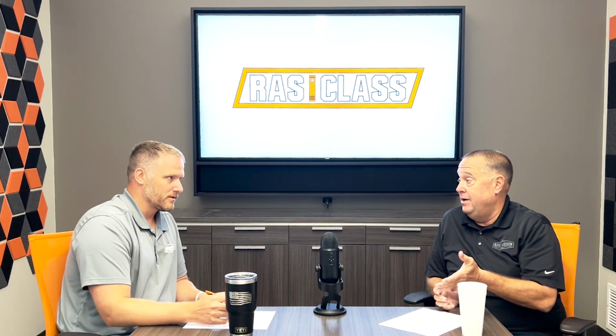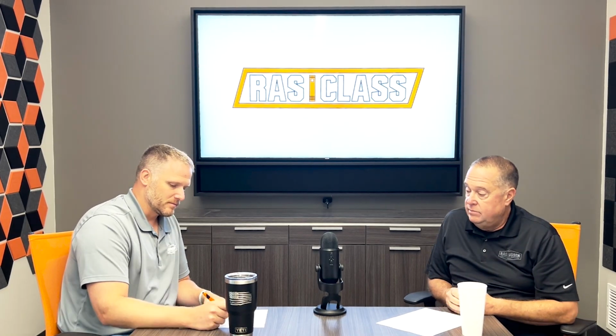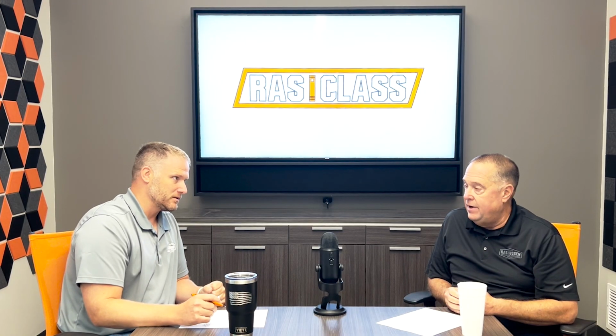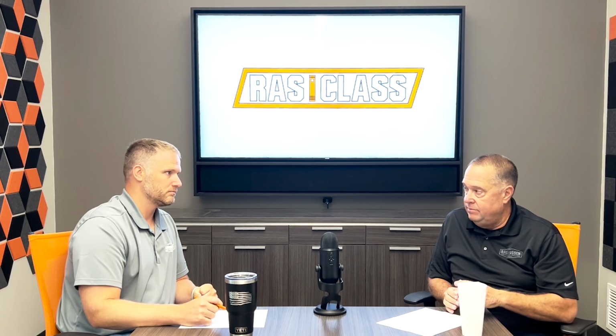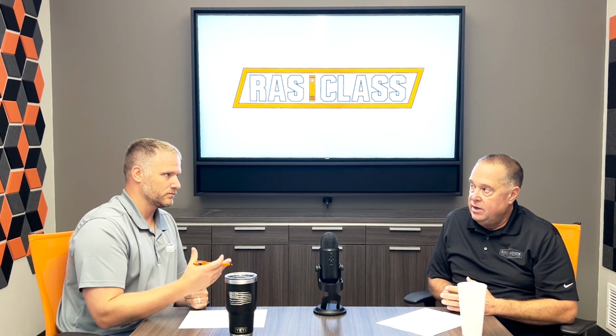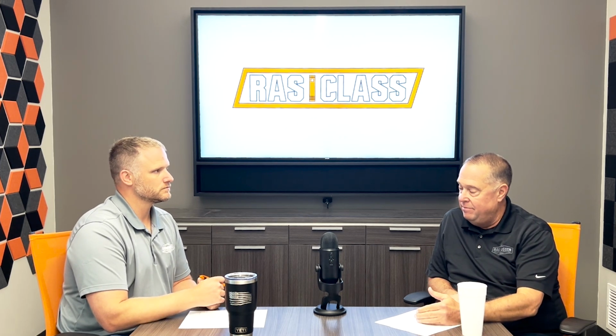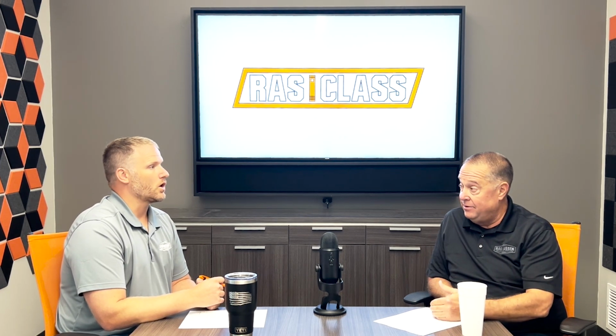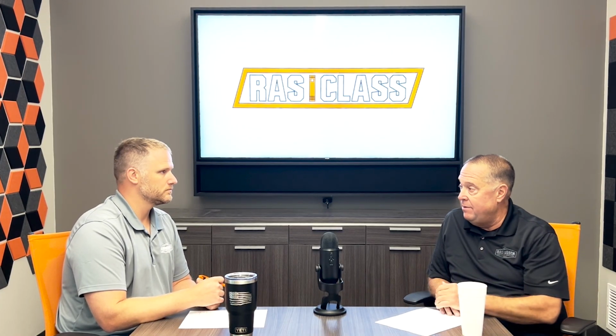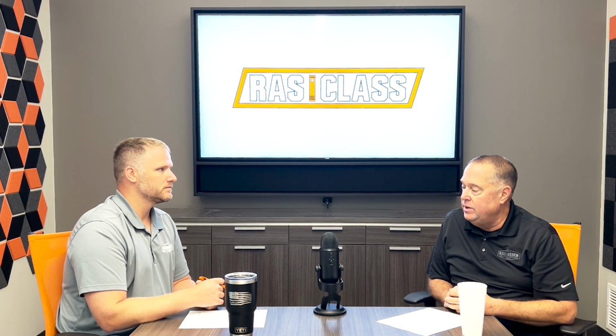Because the boiler's protected up to 399, we protect their system with an additional relief valve. But because we're buying that valve just for them, it's really their valve when we're done. It's their valve, and we just tell them, tag it and keep it. It's yours. If you're going to need a rental again, you're going to have it. And at times I'll try to identify it and make it match something they've already got. So here, you've got another relief valve. You can use this one in place. Or we try to match it up so it's not just wasted money for a one-time use.